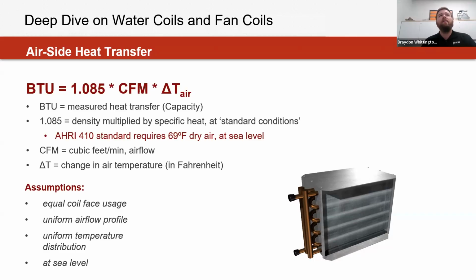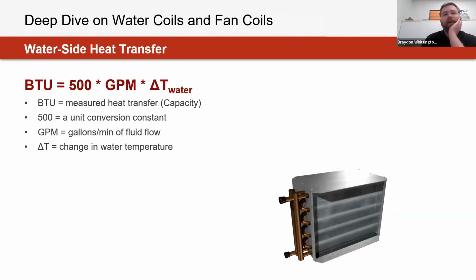Exactly. Yeah, and that's one thing that we even tie into there too. And similarly, what you're saying there, Tom, even for the water side of things there as well. Now, when we look at some of those fluid characteristics, similarly for a water side delta, that ideal condition that we might be targeting, especially when we're looking at what conditions are being fed back to your boilers within a given system, or chillers or heat pumps, key consideration for that parameter.